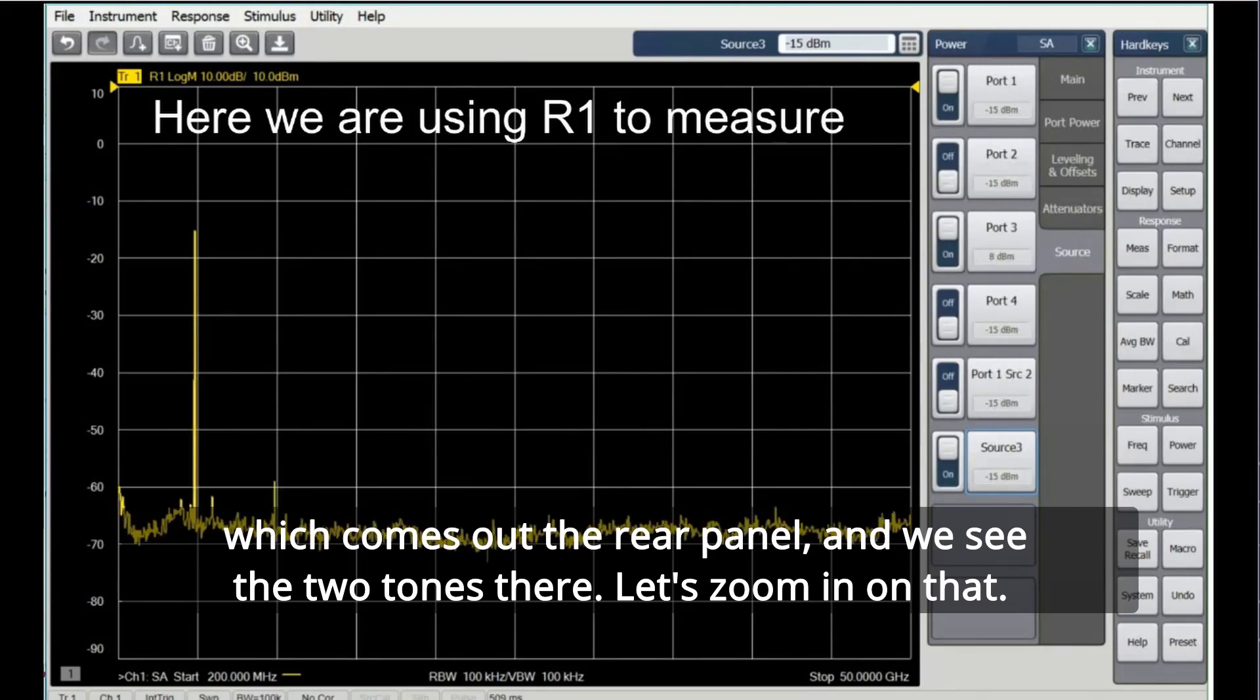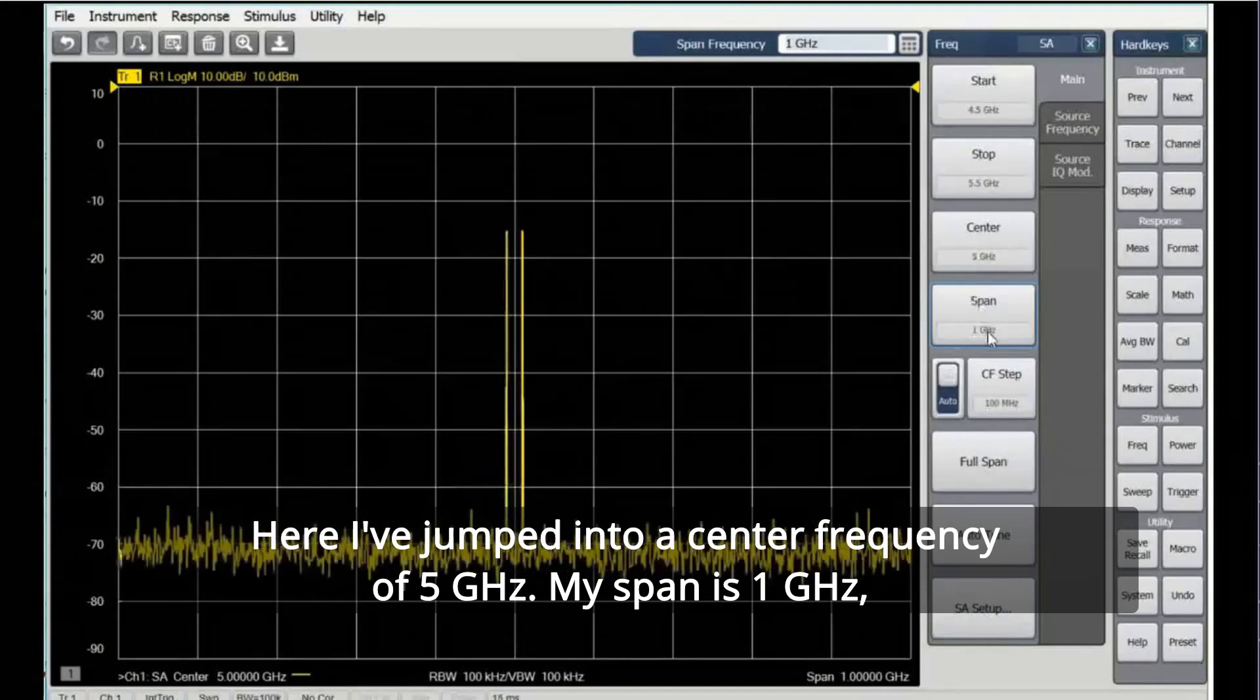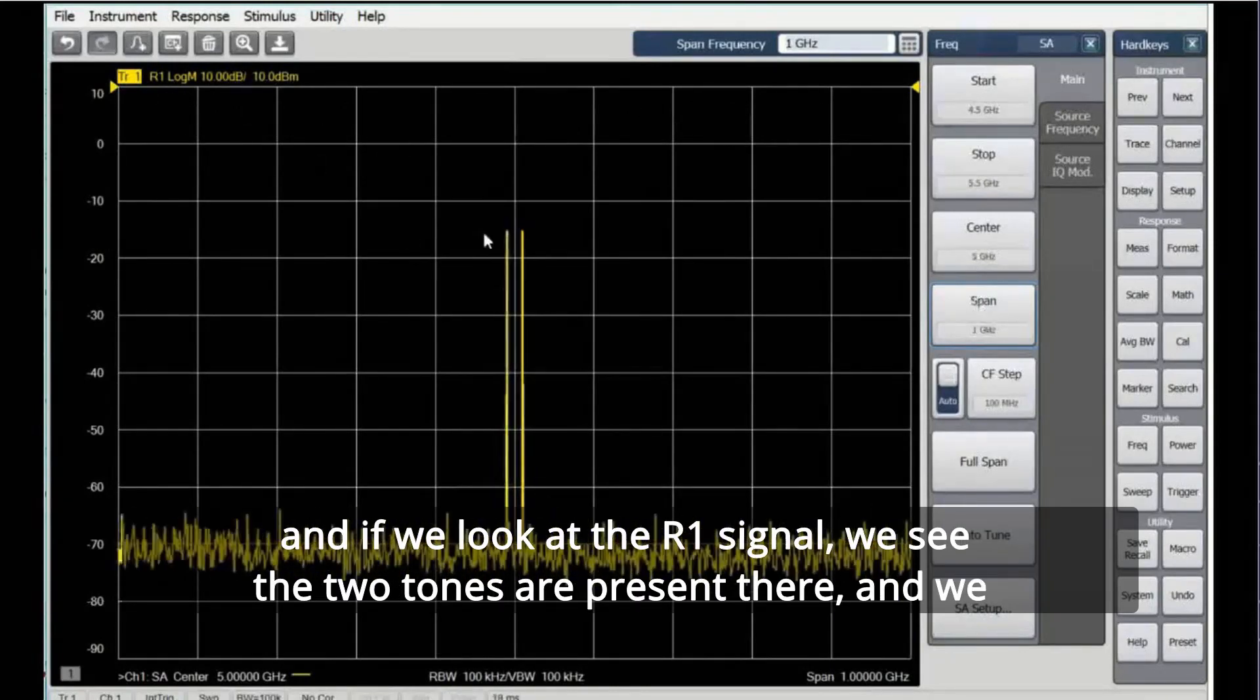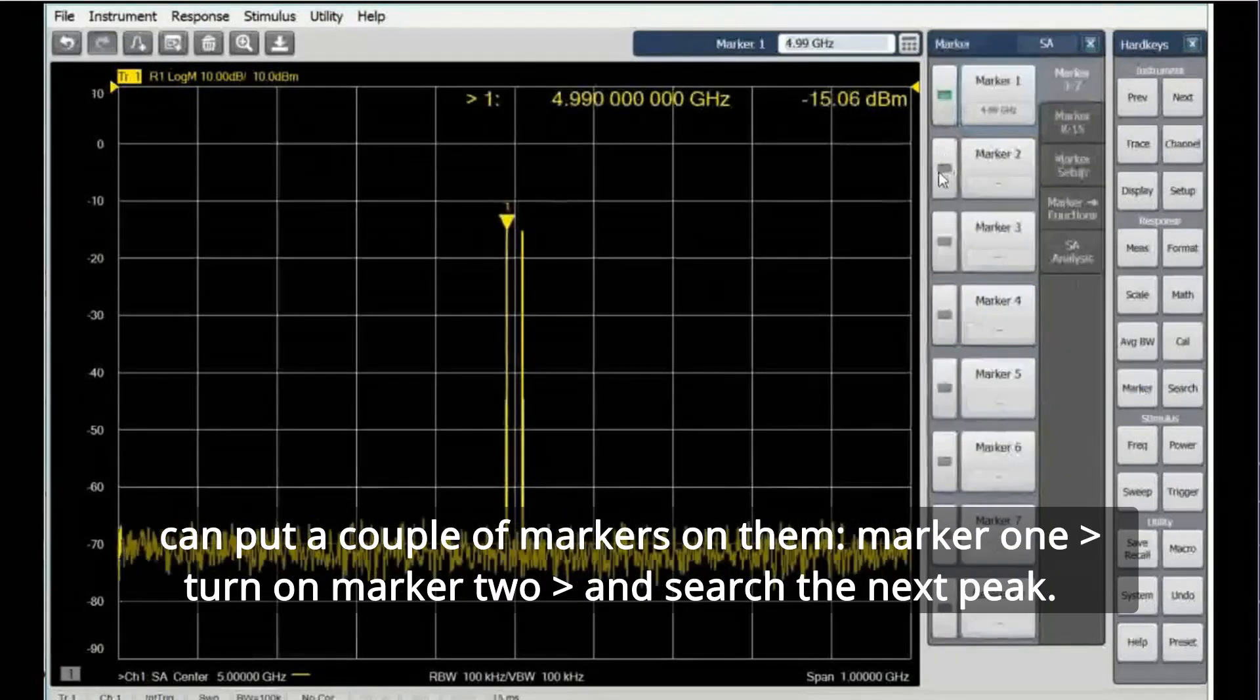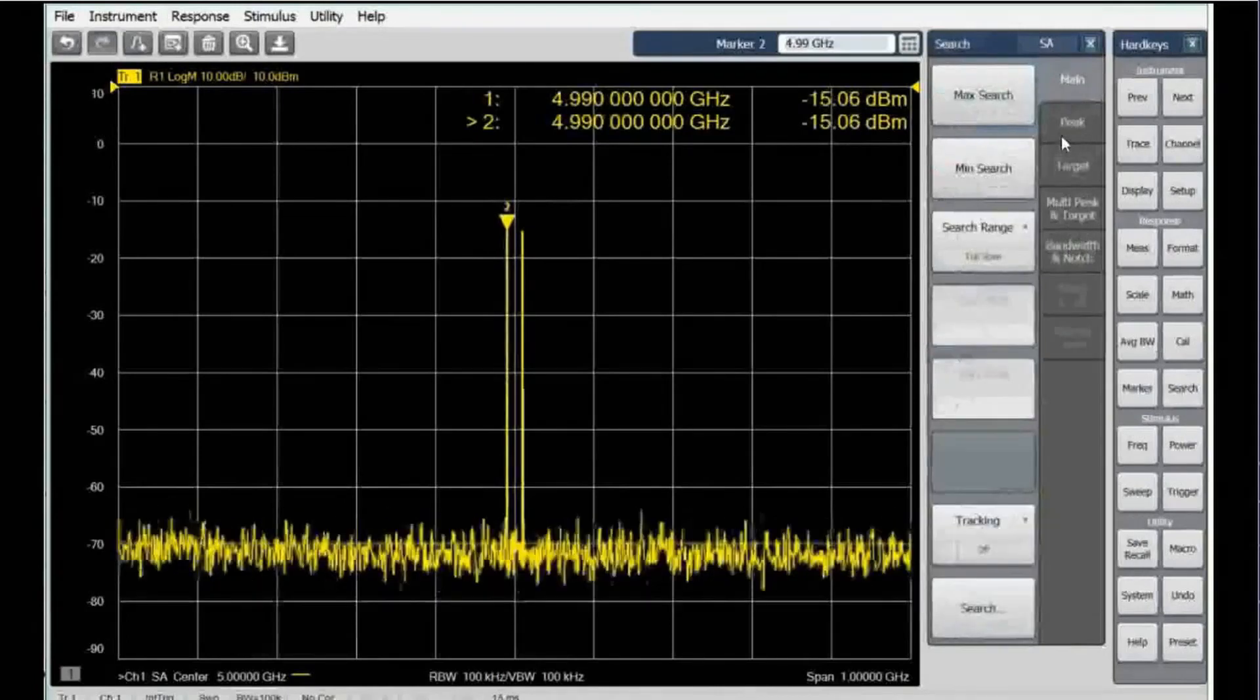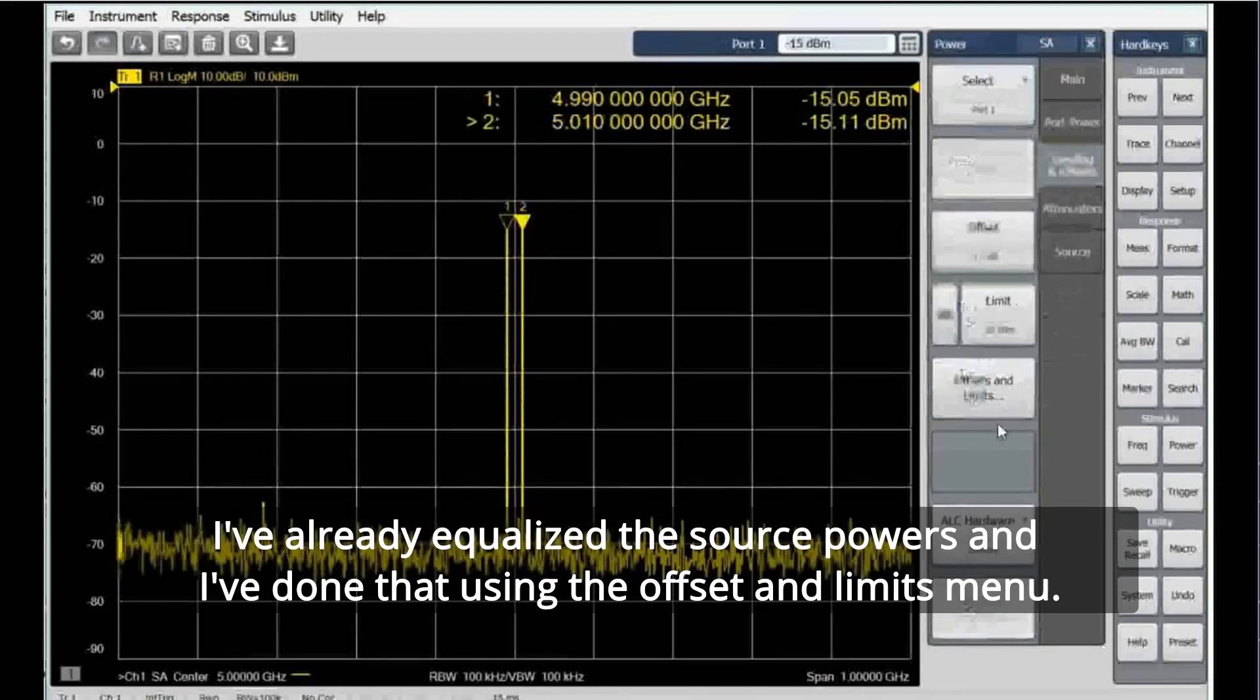We see the two tones there. Let's zoom in on that. Here I've jumped into a center frequency of 5 gigahertz, my span is 1 gigahertz, and if we look at the R1 signal, we see the two tones are present there. We can put a couple of markers on them, marker 1, turn on marker 2, and search the next peak.